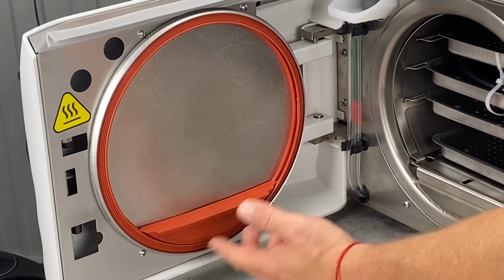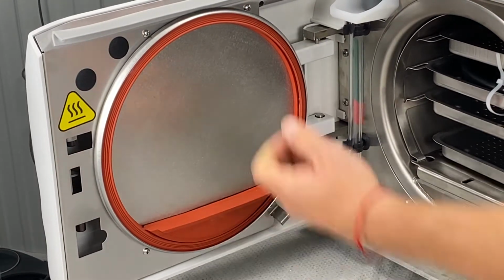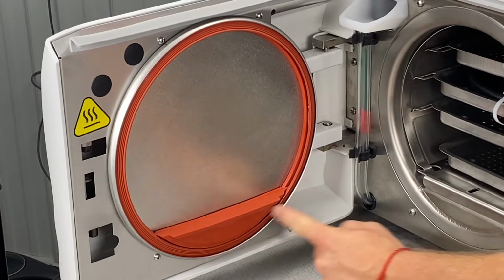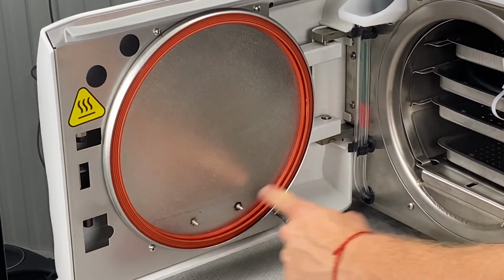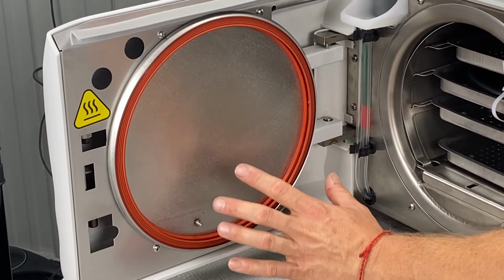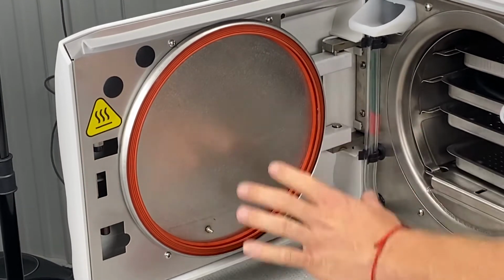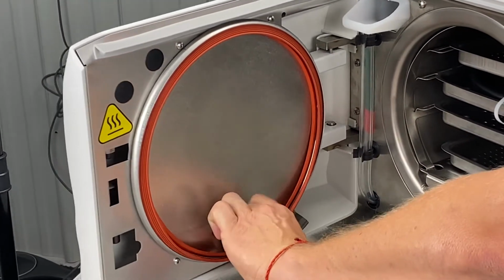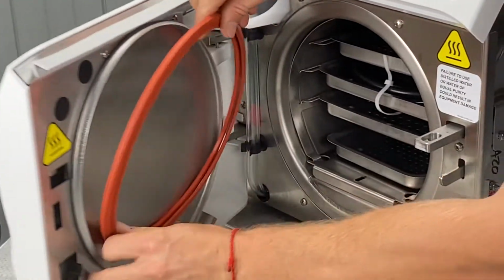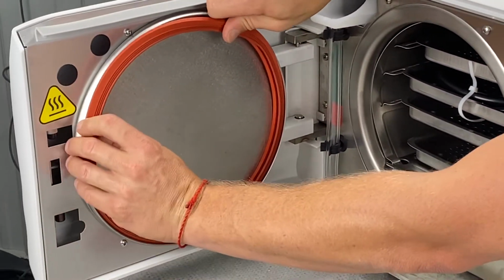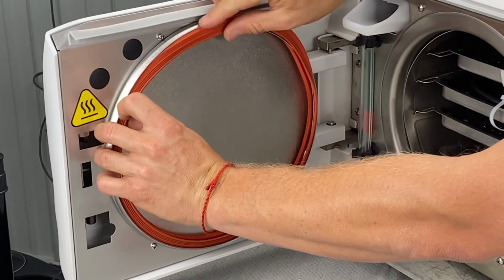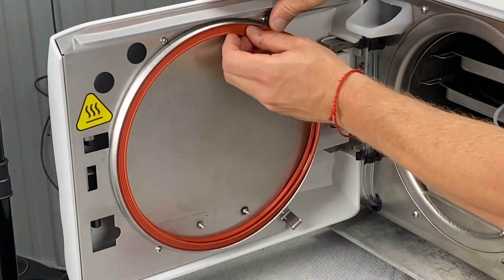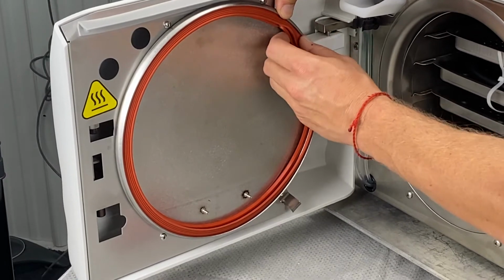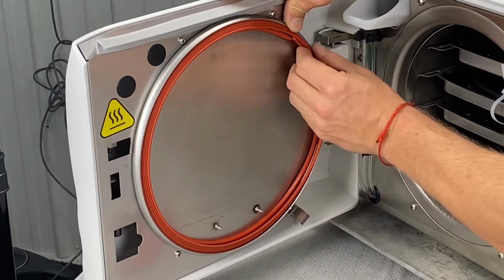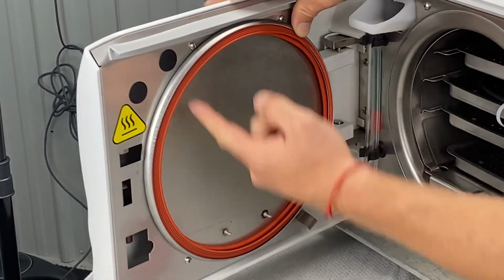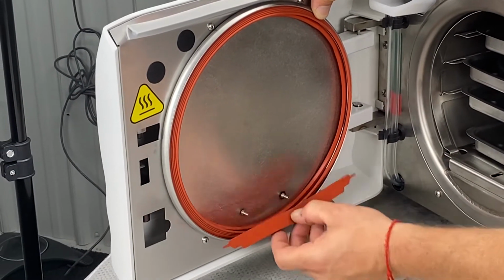We could have issues if you pulled it out and cleaned it, this gasket will warp from here to here after it sits here for a long period of time. So if you pulled everything out and cleaned it and then flipped it around, so where this was up here like this, then that could cause a leak. It's terrible, but it could. So if you have this problem and you know that you pulled the gaskets out, then just double check. You can pull it out. You can see it warped because this is fatter. And you can see it warped.